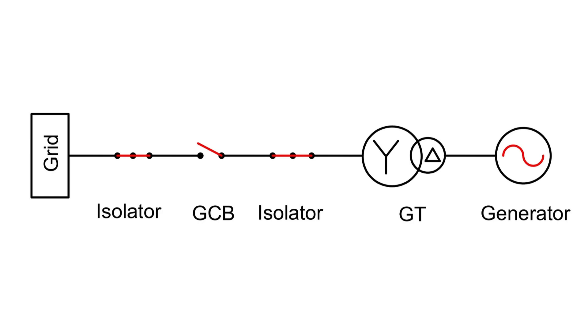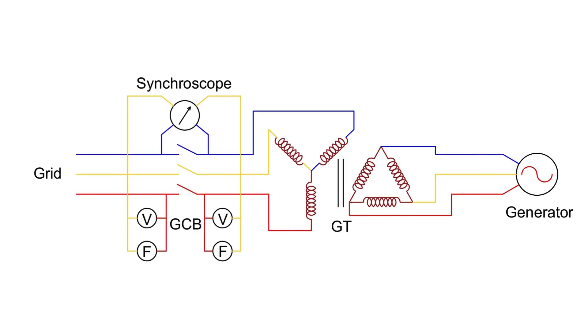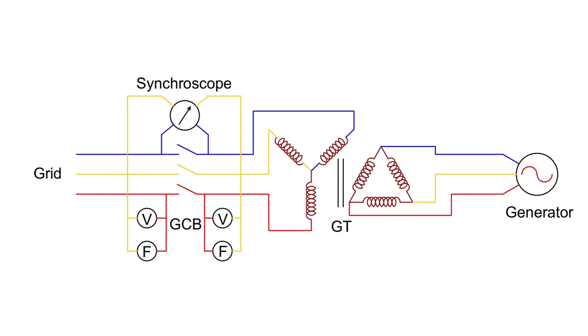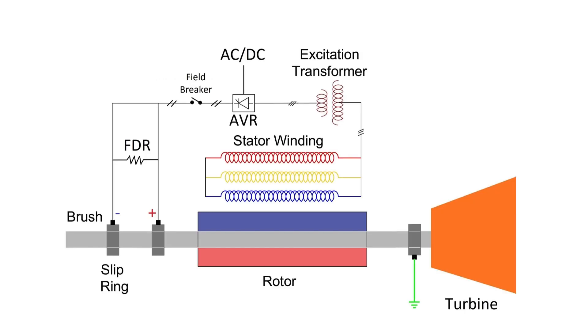For synchronization, first the isolators are closed and then the close command is given to the GCB. But before closing the GCB, we need to check voltage magnitude and frequency using voltmeters and frequency meters on both the grid and generator sides of the GCB.